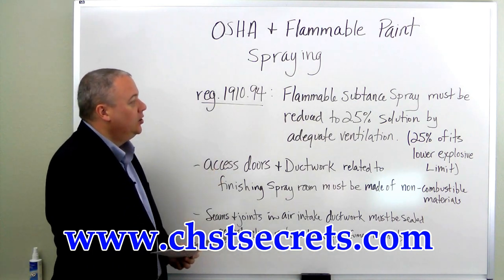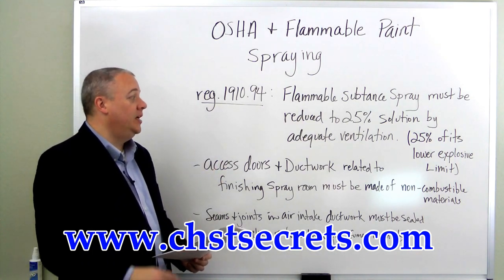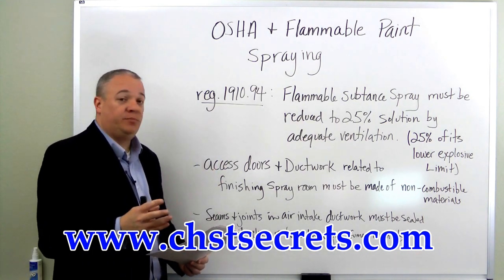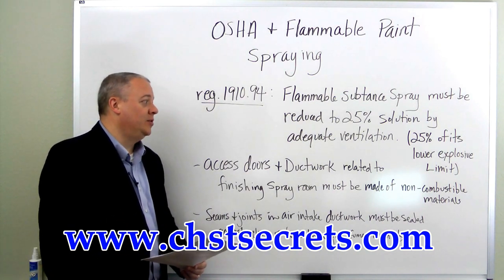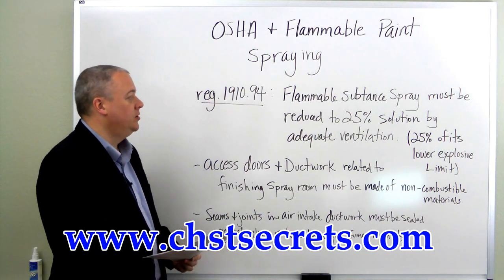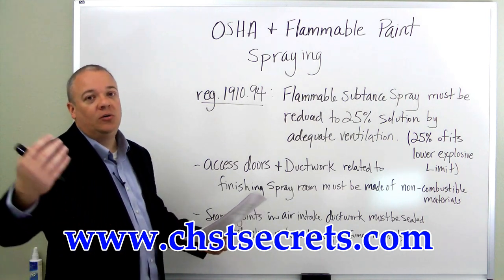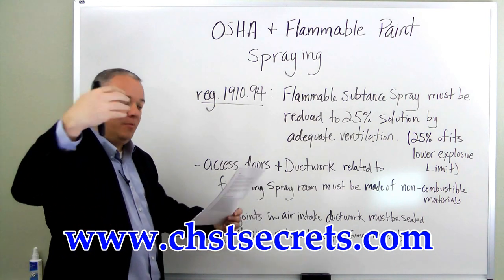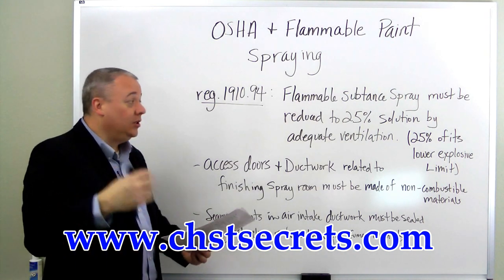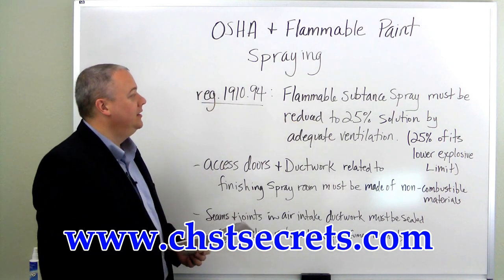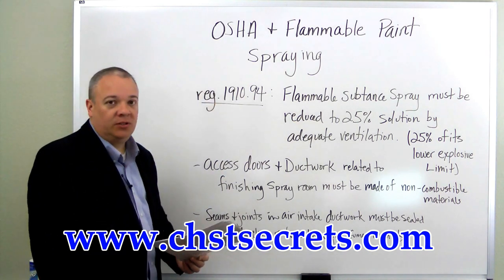What we mean by 25% solution: it must be reduced to 25% of its lower explosive limit. So adequate air must be brought in to lower the spray that's going on to 25% of that lower explosive limit.